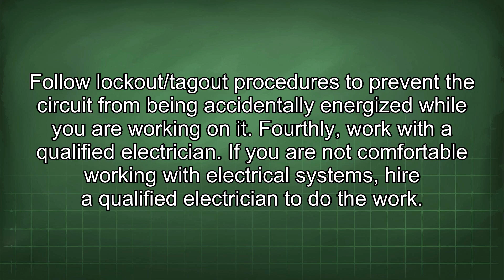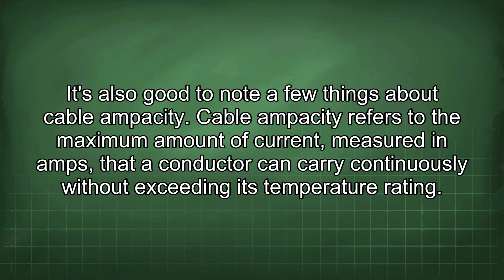It's also good to note a few things about cable ampacity. Cable ampacity refers to the maximum amount of current, measured in amps, that a conductor can carry continuously without exceeding its temperature rating. The NEC provides ampacity tables that specify the allowable ampacities for various types of conductors based on their size, insulation type, and installation conditions.